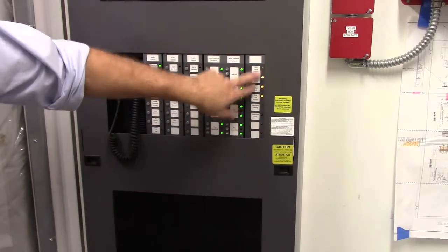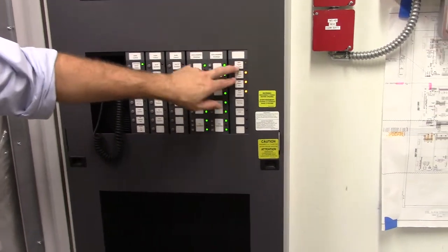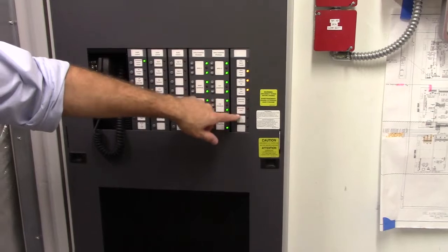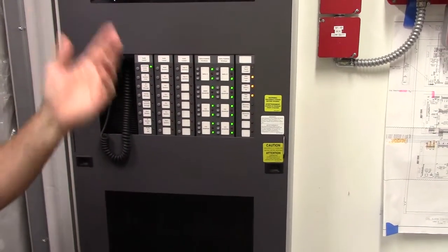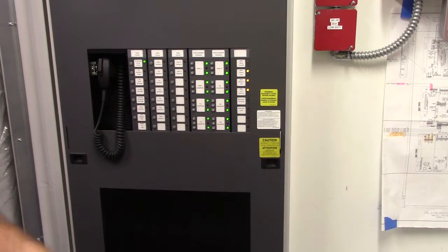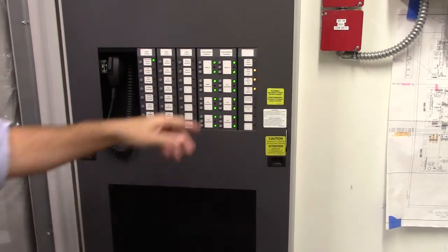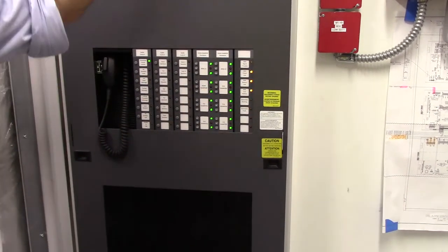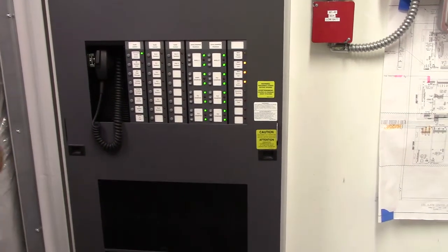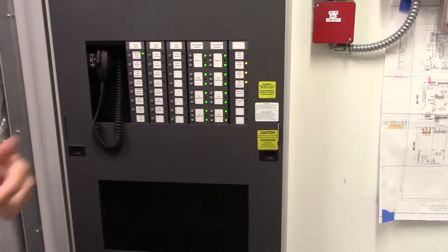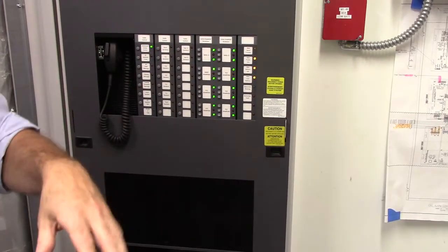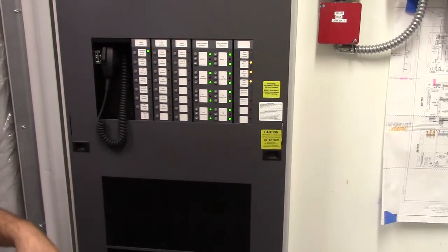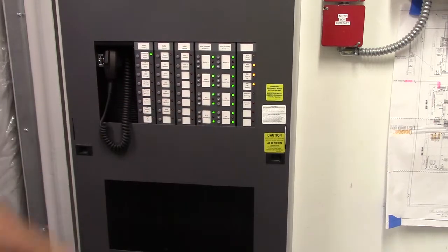Over here, these are strictly indicator lights showing you whether your BDA system's in trouble or your generator is running. I've already talked to Ted about that, and that's something we're going to be bringing up after the fact, because the spec calls for that they want this to create a trouble, but where the city box is doing it, your weekly generator test is going to create problems. So we're going to be doing the networking. We'll probably correct that once the building is officially you guys's and you've got control over it. But for right now, it creates a trouble.